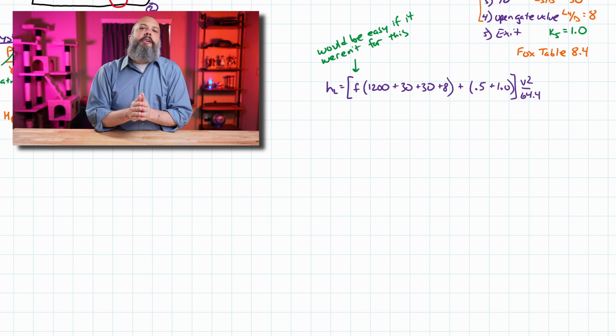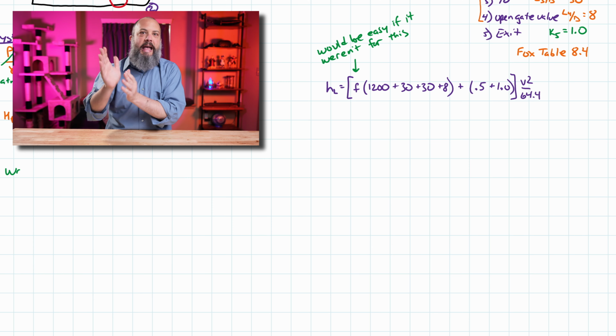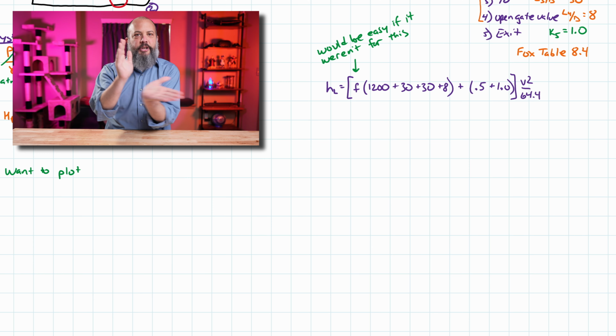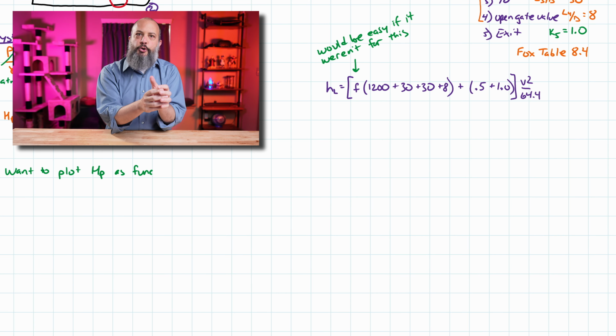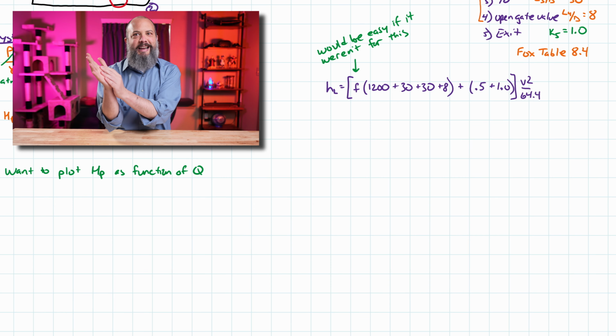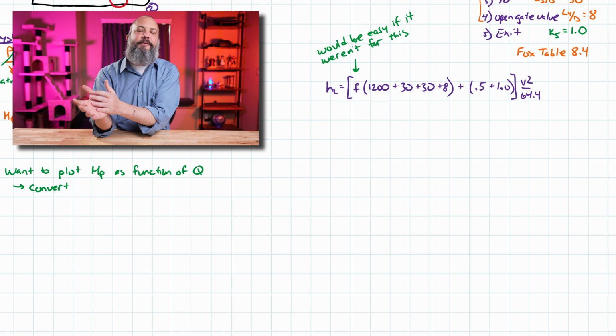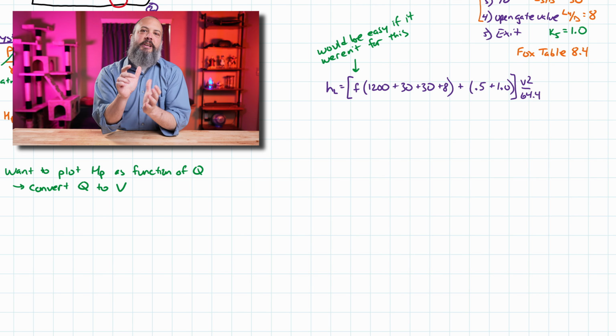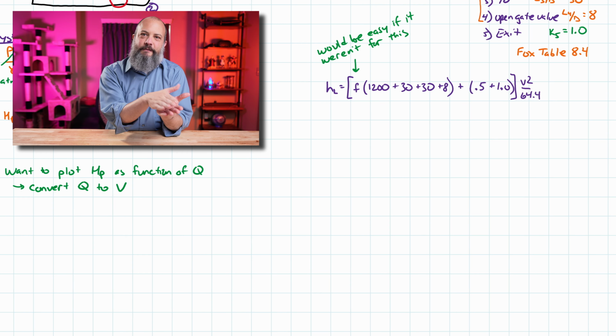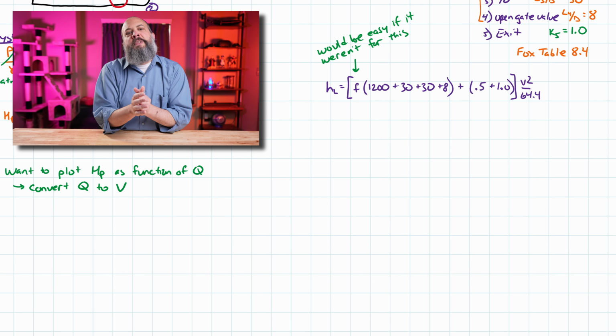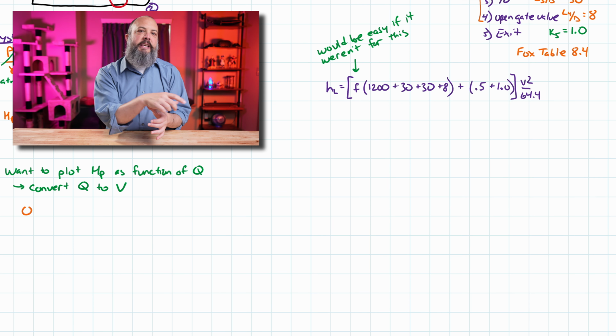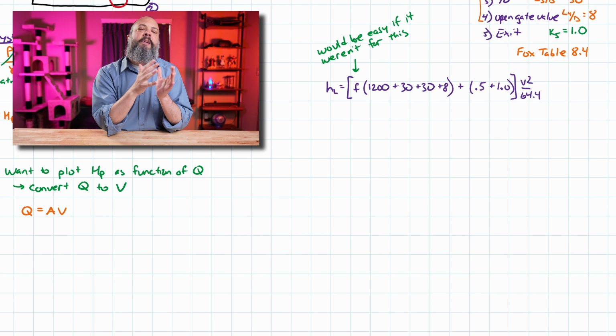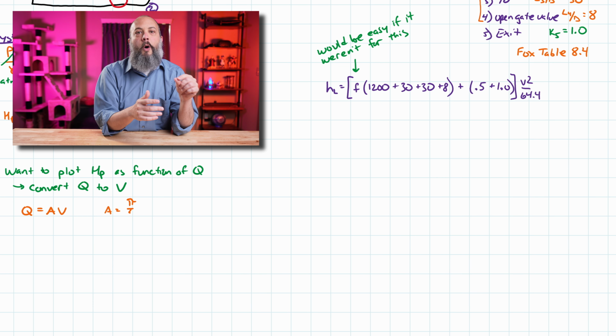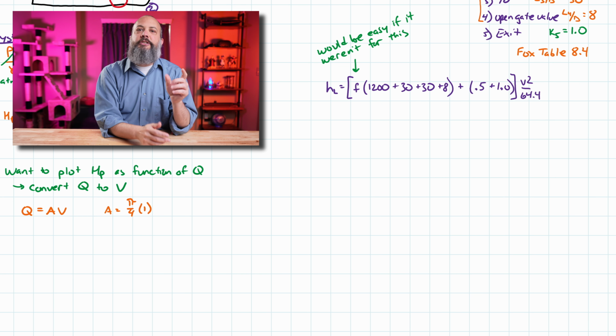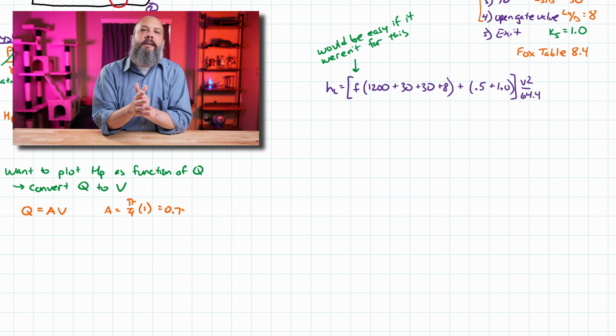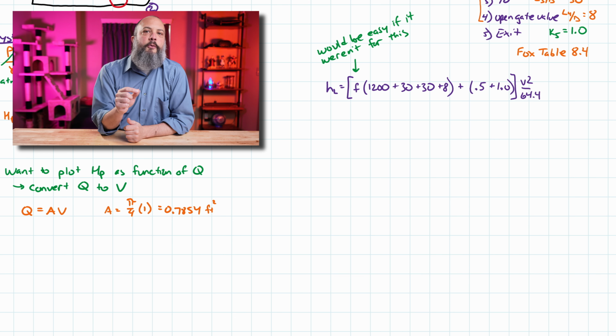Ultimately, what we're trying to do here is plot pump head on the vertical axis versus Q on the horizontal axis. So Q is our input, and Q is not even in this friction equation for head loss. So we're going to have to convert Q to velocity. Velocity is in the equation. Q is A times V, cross-sectional area times velocity. Our area is pi over 4 times 1 squared. The 1 is 1 foot, not 12 inches. We're using feet. So we get 0.7854 feet squared.